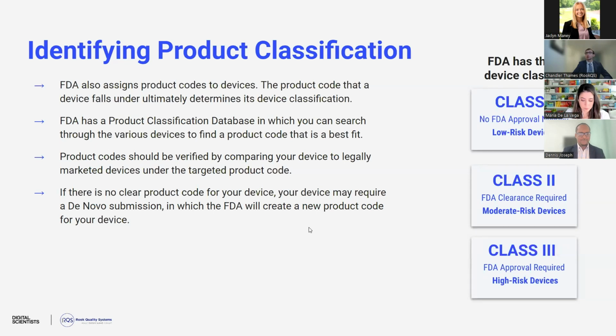So for these product codes, FDA has designated 3 device classes. Class 1 are low-risk devices. Most times these don't require any sort of FDA approval or clearance. There are some exceptions to this where Class 1 devices might require a 510K, but they're a bit more rare than the ones that wouldn't require any sort of regulatory review.